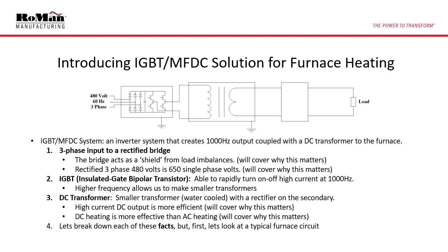An IGBT MFDC system is an inverter control that creates 1000 Hz output coupled with a DC transformer connected to the furnace. Let's look at each component of the system closely. We start out with a balanced three-phase input. A note here states 480 volts. However, other standard voltages can be used. This three-phase input is then rectified onto a DC bridge. This bridge and capacitor acts as a shield from inductive loads and imbalances on the heating element side. Rectified three-phase 480 volts is converted to single-phase 650 volts.